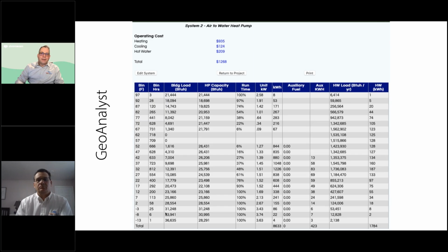So in this case, in Syracuse, all the way down to 17 degrees, it's still cycling, which is pretty impressive. When it gets colder than that outside, then it starts to load match, and then finally at -3, it runs out of capacity, so it starts bringing on some backup heat. When it gets all the way to -13, that's as cold as it can run, but it doesn't have any bin hours for Syracuse, at least below -13. When we look at colder temperatures like Winnipeg, we would see some hours below -13, and at that point, we would have to depend on the boiler or the immersion heater for heating. Next slide, please.